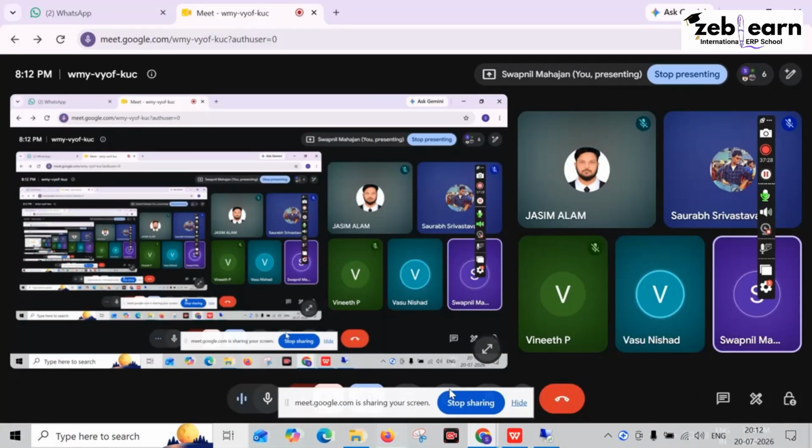Any doubts? So this is very important master data, the task list, because it has applications. We can use it in the maintenance plan. We can use the task list in auto generation of preventive maintenance orders. At that time, in the operation field of the maintenance order, there is no requirement to fill any data. From the task list, the system will automatically pick the data, and whatever task or operation is needed for preventive maintenance will get automatically updated.